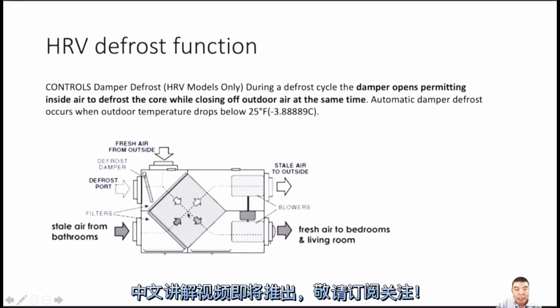And then it runs like normal. The fresh air comes in, goes through the heat exchanger, gets heated and goes to the inside of the house. And the stale air, it doesn't matter from where, goes through the heat exchanger, cools down and goes outside the building. But if, for example, outside is very cold, we have a temperature setting here, automatic damper defrost, when the current outdoor temperature drops below 25 Fahrenheit. If it is below that, the control board will tell it how long it needs to defrost.